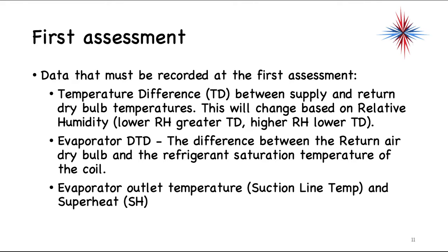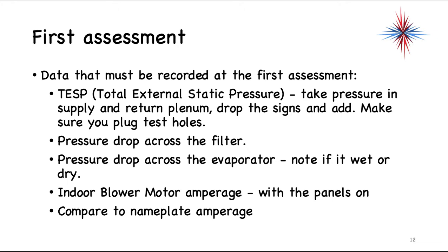The evaporator design temperature difference is between the return air dry bulb and the refrigerant saturation temperature of the coil. Record the evaporator outlet temperature — that's the suction line at the evaporator — and get superheat while you're there. Take total external static pressures: pressure in the supply duct plenum plus pressure in the return plenum, dropping the signs and adding the absolute values together. Make sure you plug any test holes you make — put a plug in it, because you'll use these holes in the future. Note the pressure drop across the filter and across the evaporator, noting whether the coil is wet or dry.